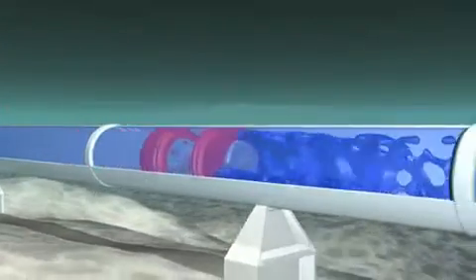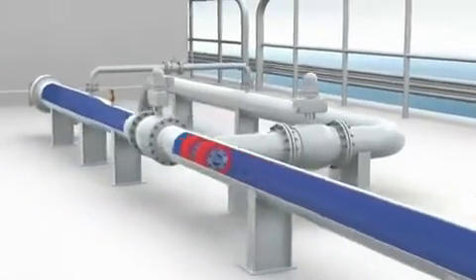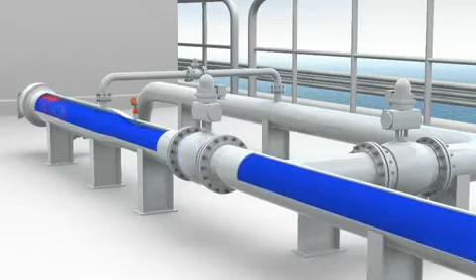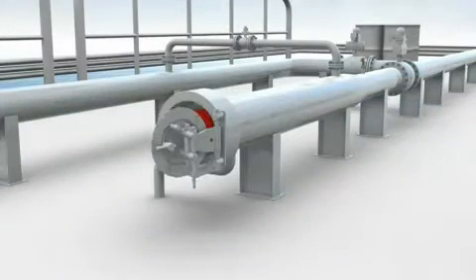As the pig approaches the receiver, a signaler trips. The pig enters the receiver. The pig trap isolation valve closes, and the trap is drained. The closure door is opened, and the pig recovered.